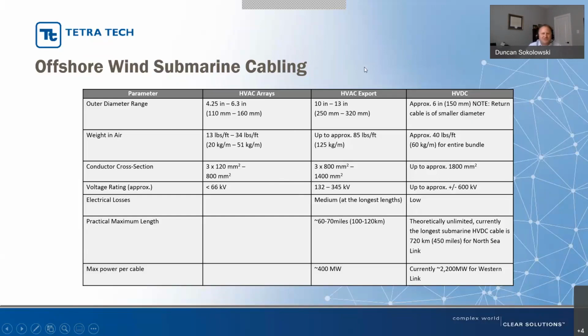If we look at the export cables, which take the power from the entire wind farm to shore, and we're talking about AC cables, they are quite a bit larger - up to about 13 inches external diameter, weighing roughly 85 pounds a foot or so in air, with conductor cross-sections of about 800 up to a maximum of say 1,400 square millimeters. Voltage range is also a lot higher, about 132 to 345,000 volts, which means they can transmit power over a longer distance with less electrical losses.